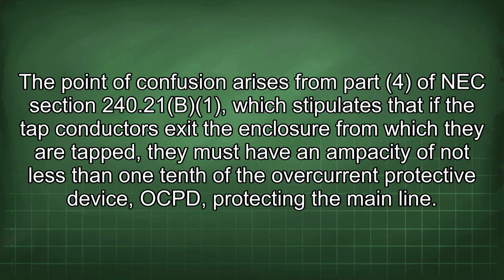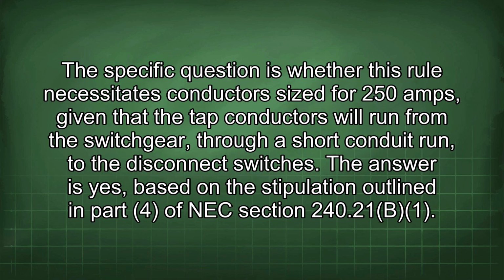The point of confusion arises from Part 4 of NEC Section 240.21(B), which stipulates that if the tap conductors exit the enclosure from which they are tapped, they must have an ampacity of not less than 1/10 of the overcurrent protective device, OCPD, protecting the main line. The specific question is whether this rule necessitates conductors sized for 250 amps, given that the tap conductors will run from the switchgear through a short conduit run to the disconnect switches.